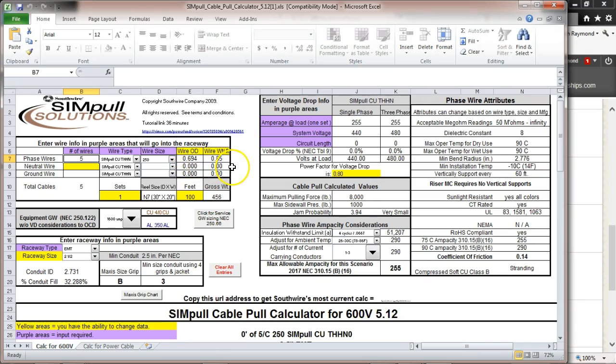And then this right here would give you the wire weight per foot. Then we would come up here, and you see the pull tension would be 8,000 pounds. With this sidewall pressure, jam probability would be very small for this size cable.